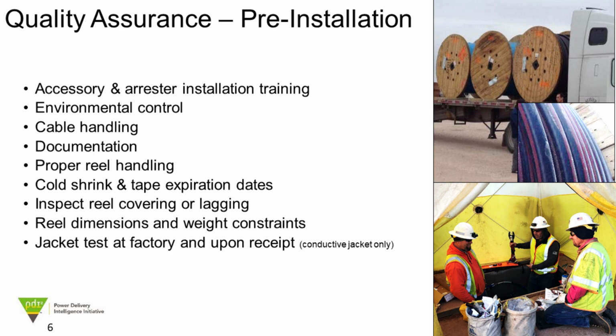The idea is do the right steps, including the cable handling, including the documentation, of course, including the training. Don't get people who don't know what they are doing and then discover that they did a bad job. Yeah, that's great to discover that they did a bad job and you fix it before you energize the system. But that's not the point. The point is make sure that the steps are followed properly, and then put the icing on the cake by doing a commissioning test to ensure that nothing is left to chance. So people should not rely on the test to catch the problem because they were careless in the installation phase or in the handling phase.